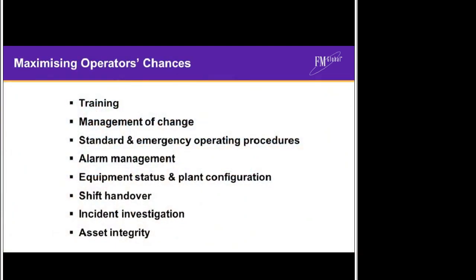Maximizing operators' chances of responding successfully to an upset condition is a combination of factors. Quality of their training and retraining is clearly very important. So too is the management of change on the plant. Detailed yet easy to follow emergency operating procedures will enable an operator to take the correct actions during an upset condition and thus minimize the impact on the plant. Thorough and diligent alarm management also allows operators to focus on important information without having to acknowledge standard notifications that are not in fact alarms.